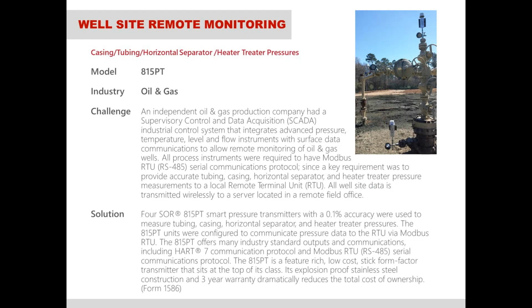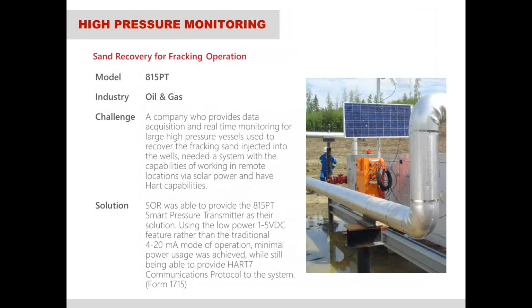Well site remote monitoring. There are a lot of well applications out there that are remotely located and don't have ease of access to power. Those products will often require solar power or a battery to operate, where the power is quite limited. So they'll use our transmitter in a 1 to 5 volt DC mode output. This fixes the current at a very low power requirement to utilize the solar power most effectively. High pressure monitoring on sand recovery for fracking operations is another remote application where they're running off a solar panel and need to use as little power as possible.